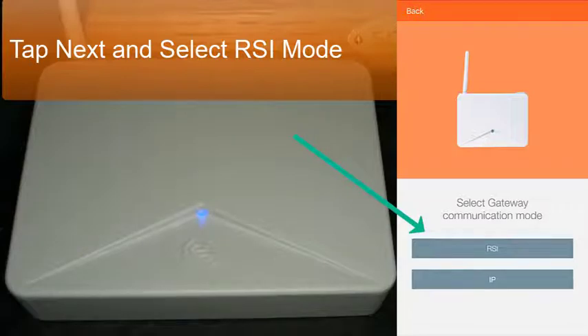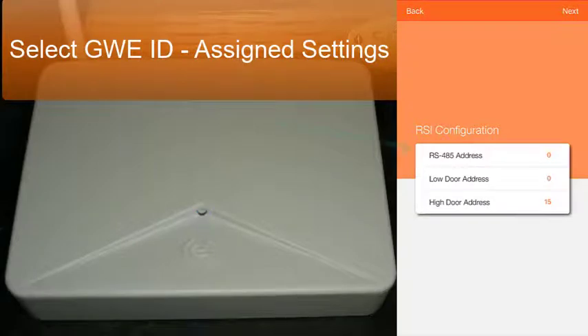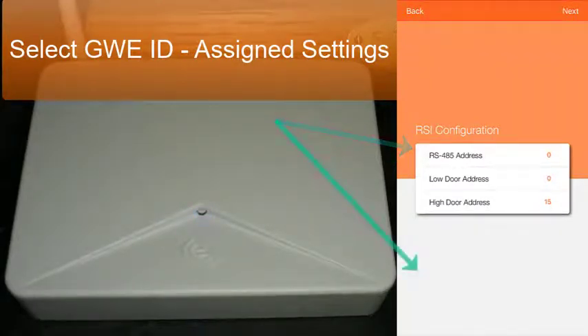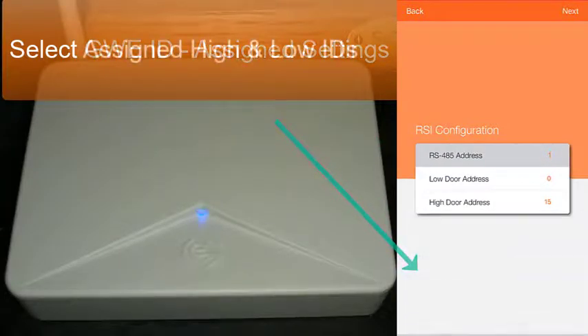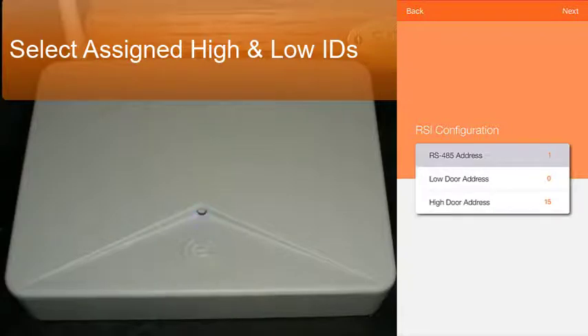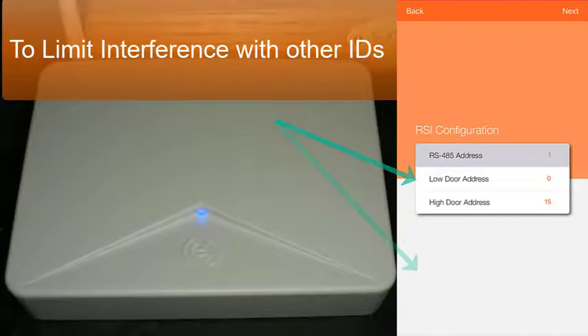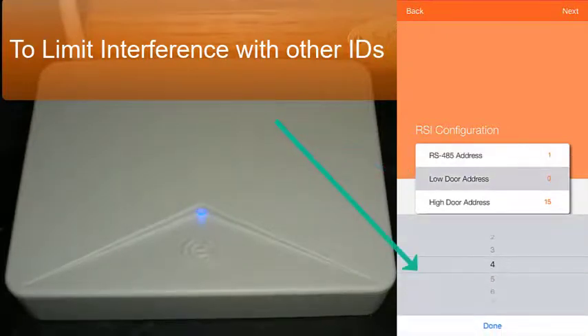Then you select the RS-485 ID address that has been assigned — in this case we are going to assign one. Confirm the RS-485 high and low ID boundaries so that each ID is unique for the access control panel assignment for each lock that will be linked, without adding extra IDs on the gateway causing potential overlap with other device IDs configured and assigned to that controller. In this case we are going to assign low door 5, high door 10.